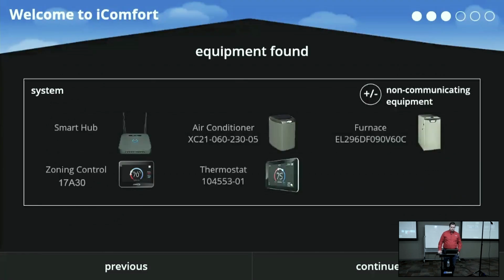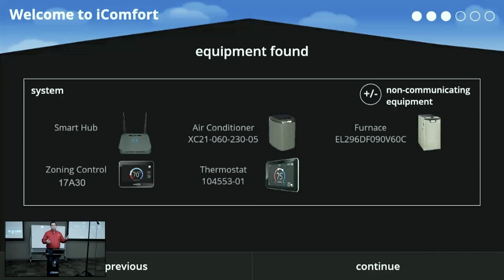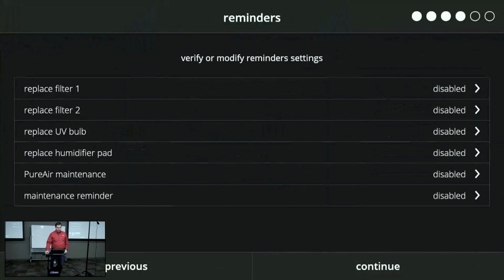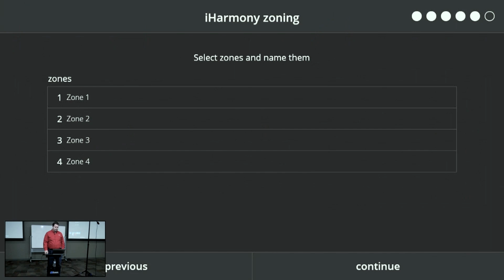This can be a critical point telling us what equipment's found. So obviously, if you're installing a system and your zone board doesn't pop up, or your outdoor unit doesn't pop up, and you've got a communicating outdoor unit, then we know we've got a communication problem. So this can just be a handy way to say, okay, it will not show all of your zone sensors, but it will show your zone board, your indoor unit, and your outdoor unit, of course.